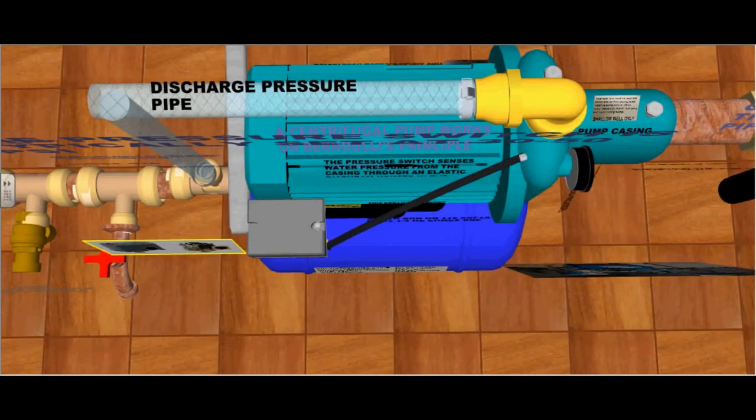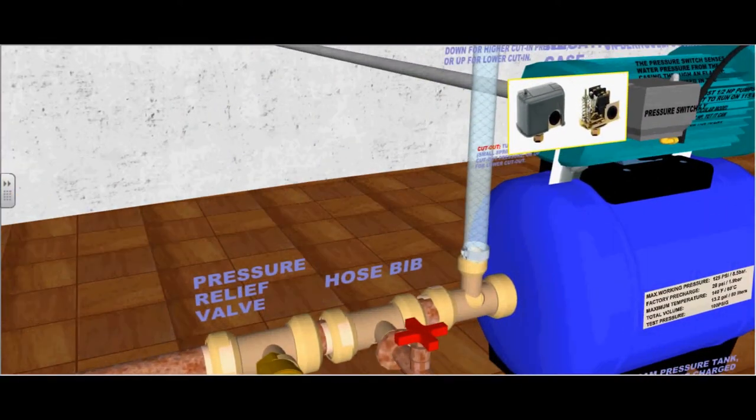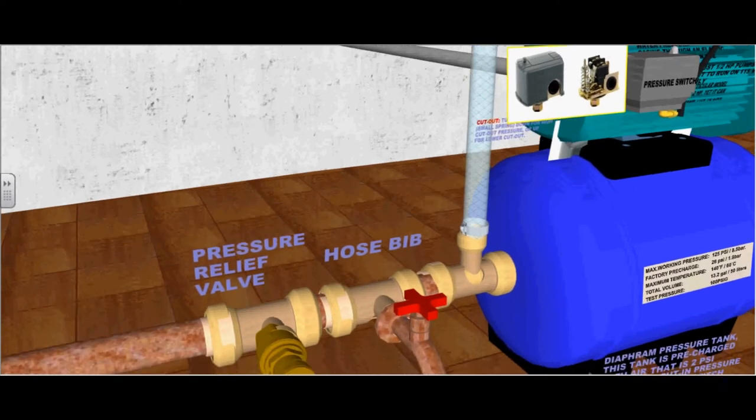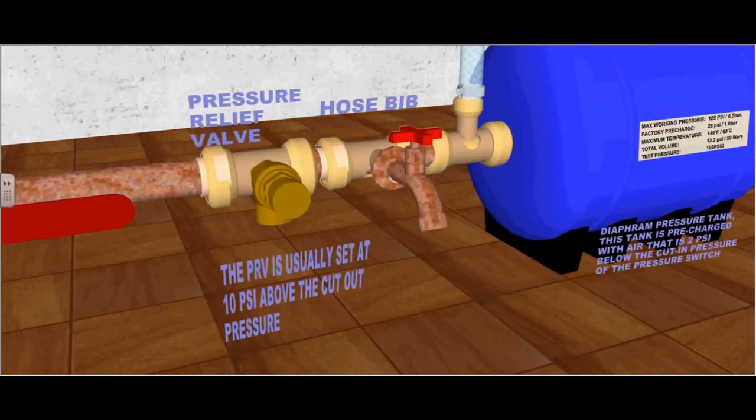This is the discharge pressure pipe coming from the volute casing. Here is a hose bib used to test the water and purge the system. This pressure relief valve is usually set at 10 psi above the cut-out pressure.